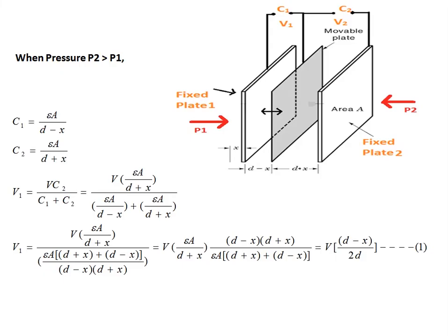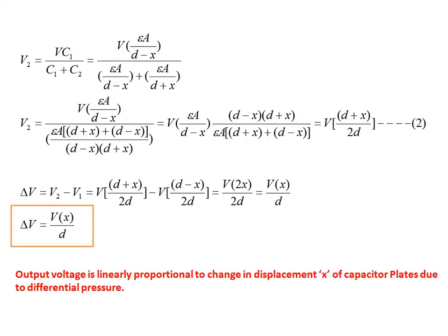Whenever pressure P2 is greater than P1, the movable plate moves towards fixed plate 1. The distance between fixed plate 1 and the movable plate becomes D minus X, and the distance between the movable plate and fixed plate 2 becomes D plus X. Deriving the capacitance and voltage equations gives delta V = V × X / D. The output voltage is therefore linearly proportional to the displacement X of the capacitor plates, caused by the differential pressure.